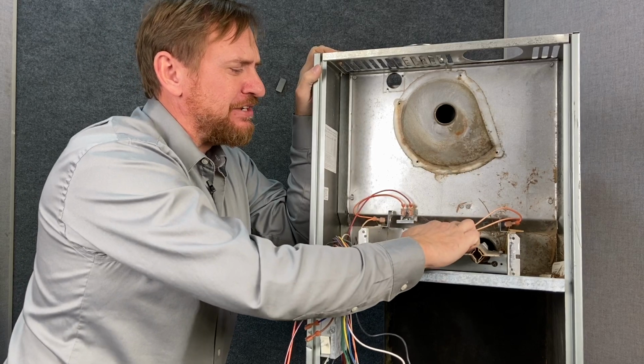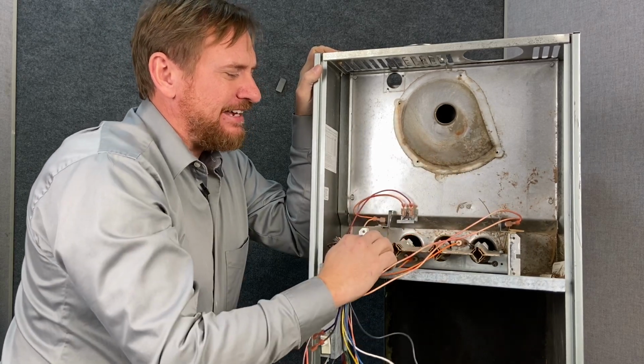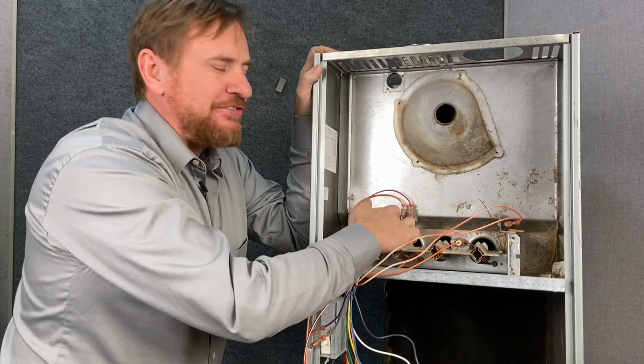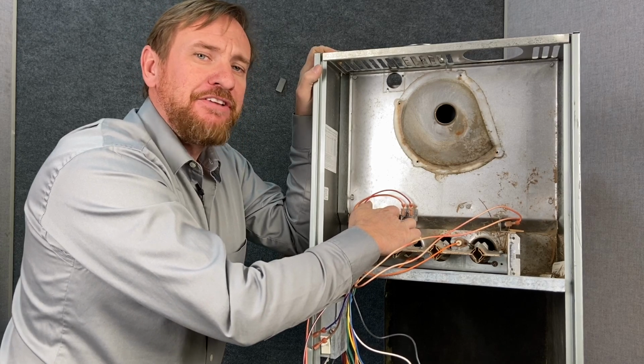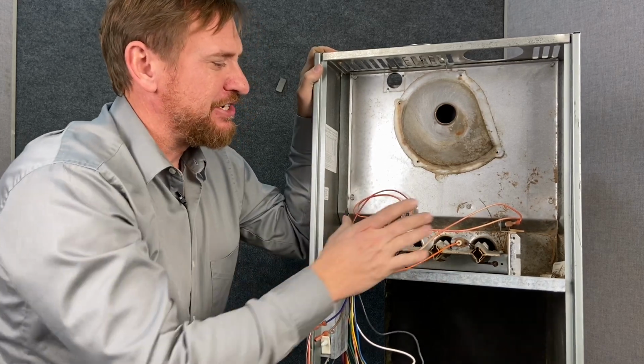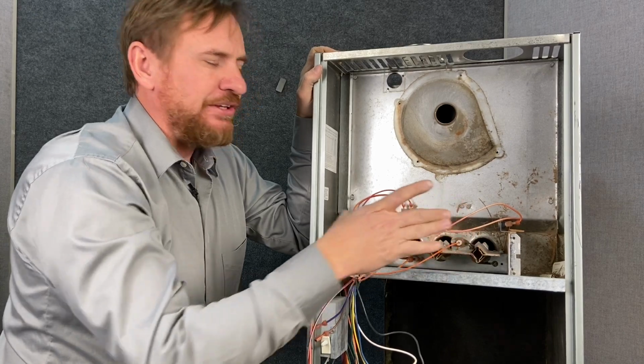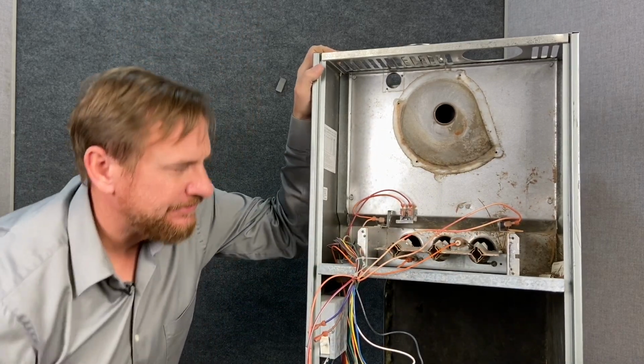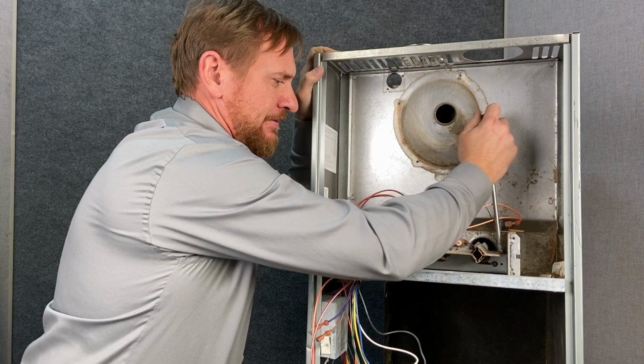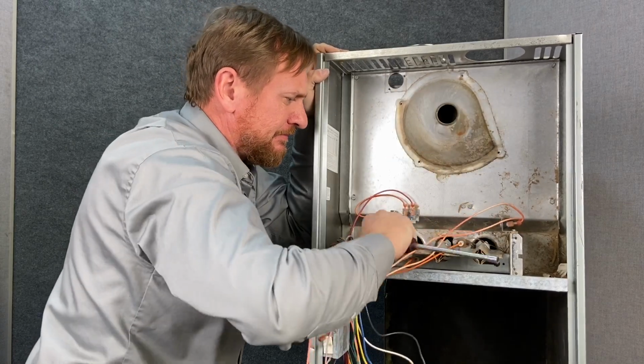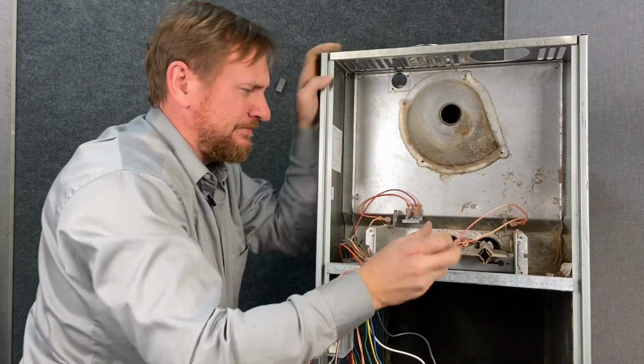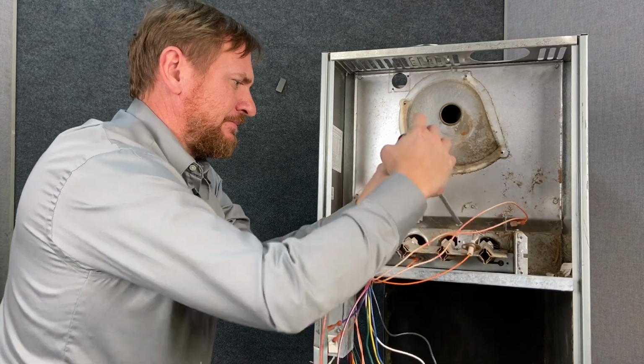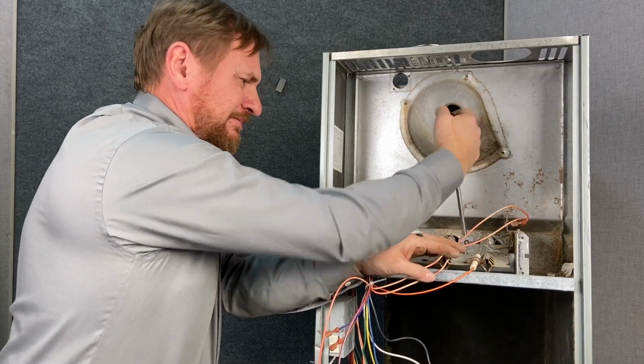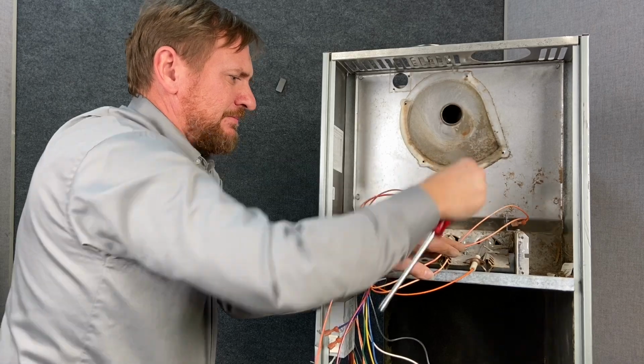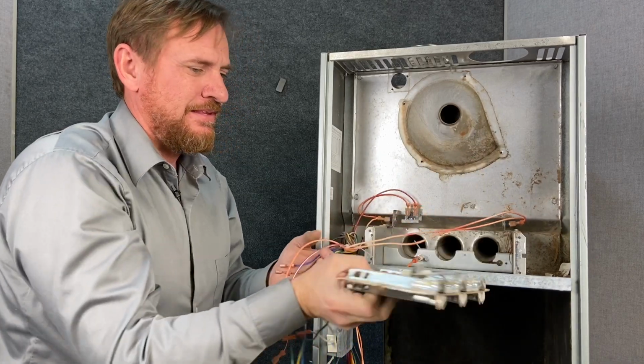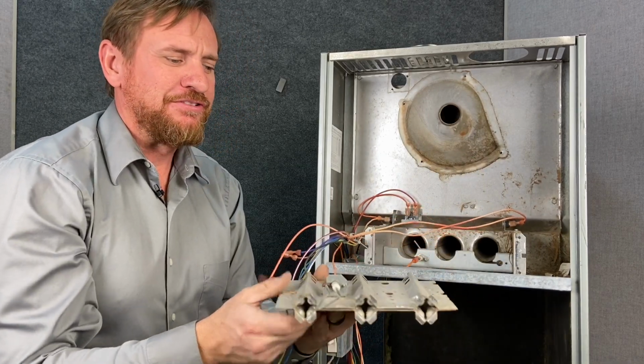This one uses an electronic ignition system to ignite that flame, and we also use a flame sensor so that we can check to prove that we have a flame through a process called flame rectification. I'm going to pull this out as one full assembly so you can see that easier. Now here we have the burner assembly.